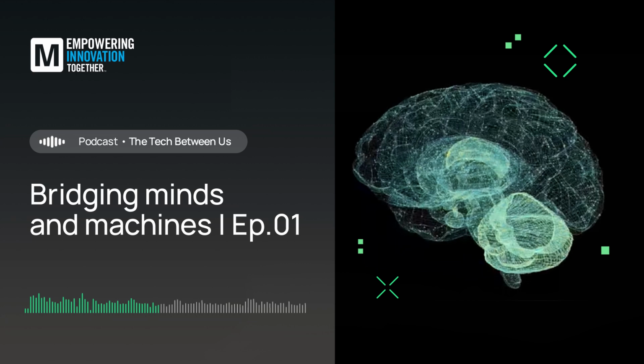So obviously these sensors are incredibly sensitive. About what voltages? Are we talking millivolts, microvolts coming directly off the brain? These are in the microvolt range. Okay, so really small. Really small. Somewhere in the 0 to 200 microvolt range is typical, depending on the quality of your sensors and how close they are to the source of your signal.